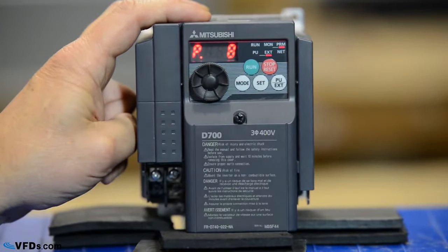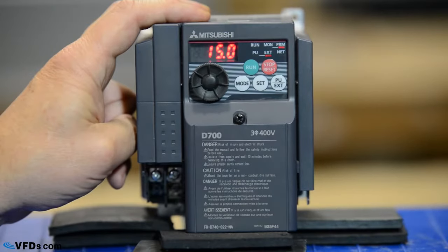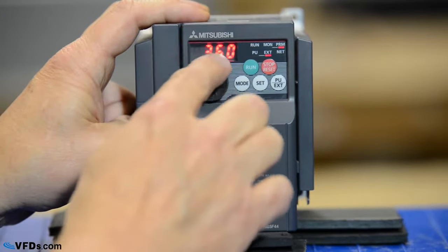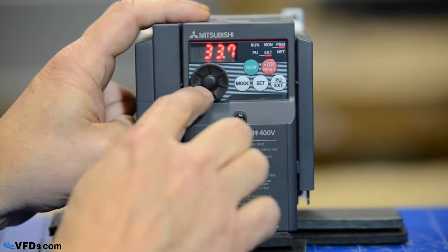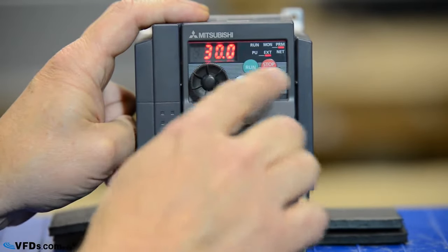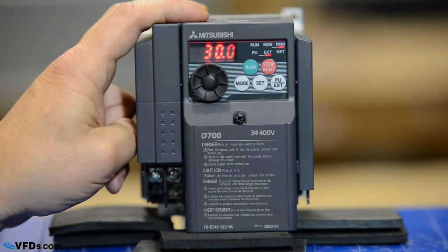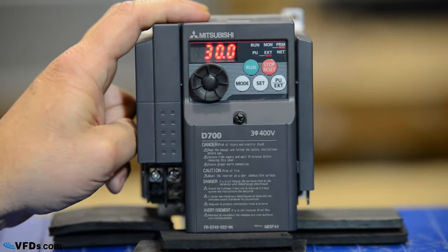My next parameter is parameter 8. That's my deceleration time. I don't want to slow down too fast, so I'm going to change my deceleration time up to about 30 seconds. Let me change this to 30. I press set again and it will now slow down from 60 hertz to 0 in 30 seconds.